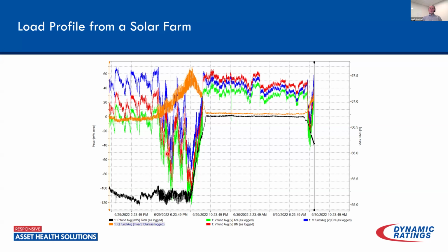But these rapid changes in voltage that we're seeing here do cause additional stress on the insulation. And of course, as they finally ramp it back down, when we're offline at this point in time, things are nice and stable. So with this type of load profile, you can see the impact: we could be looking at some harmonic resonance on the system, we could be looking at just the VAR contribution, and it could even be how they're regulating, or how they've been asked to regulate based on the ISO, for the wind and solar farms.